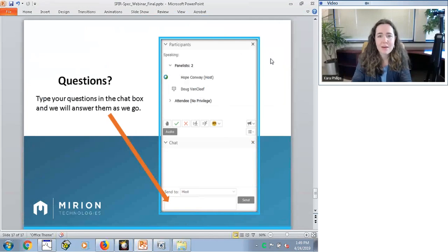One question we have is, can you access and modify the nuclide library on the device? That's a great question. There's about 7 different nuclide libraries on the device. You can create custom libraries using those existing nuclides on there. And so with over 80 nuclides on the device, it really has all the nuclides that we could imagine you might want to use to do that onboard analysis. And if you need any more, you can always come out into Genie and do the analysis there as well.